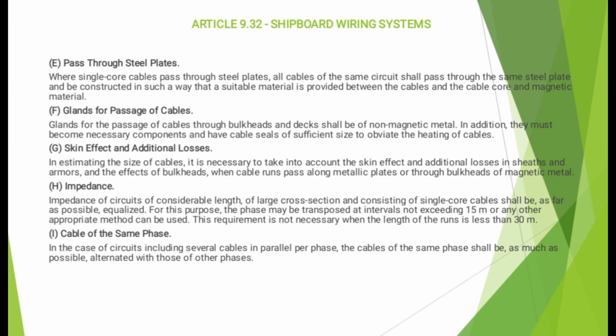In estimating the size of cable, it is necessary to take into account the skin effect and additional losses in armors and the effect of bulkheads. When cable runs pass along metallic plates or through bulkheads of magnetic metal, impedance of circuits of considerable length of single-core cable shall be as far as possible equalized for this purpose. The phase may be transposed at intervals not exceeding 15 meters or any other appropriate methods can be used. This requirement is not necessary when the length of the runs is less than 30 meters.